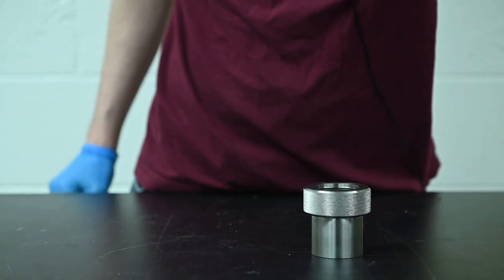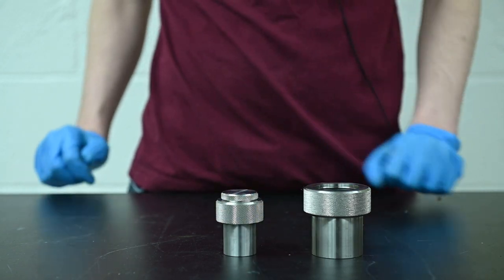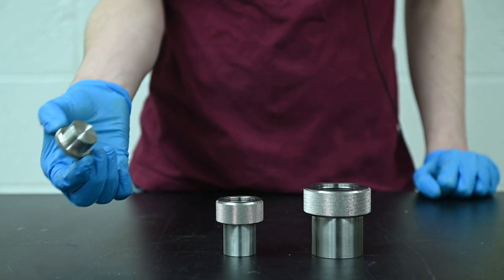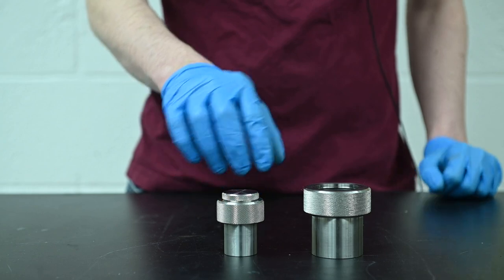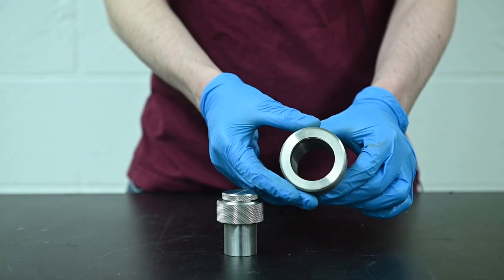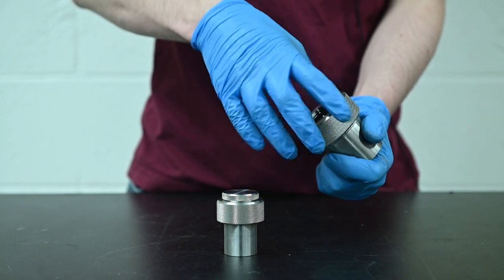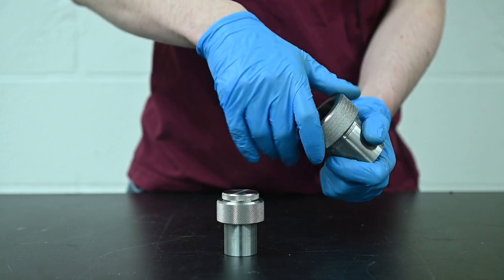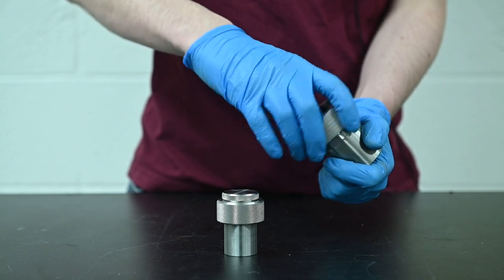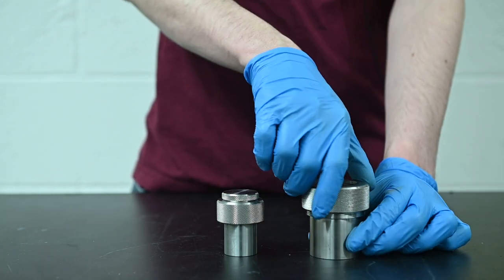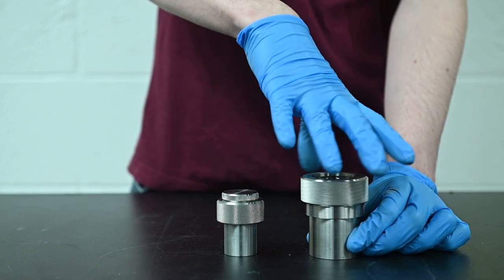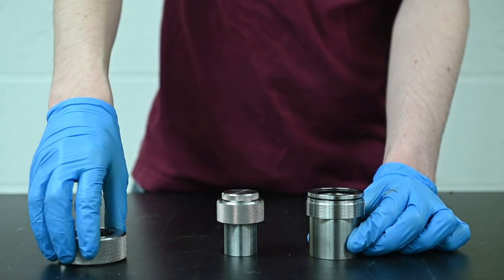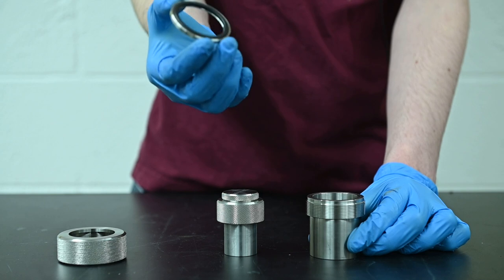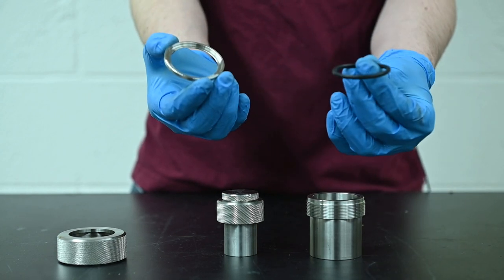Here we have two different sizes of Wilson seal. You can see that Wilson seals seal on cylindrical surfaces by tightening an external nut, which squishes an internal O-ring onto the radial external surface of a cylinder. They're often used for sealing to glass tubes and other fragile cylindrical items, like a Bayard-Alpert gauge. Wilson seals come in many different sizes, one for each different diameter of cylinder you could want to seal to.